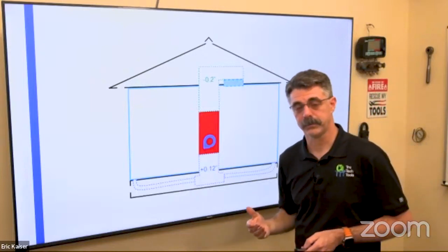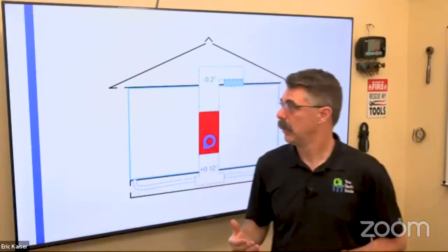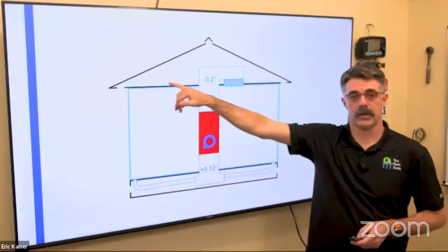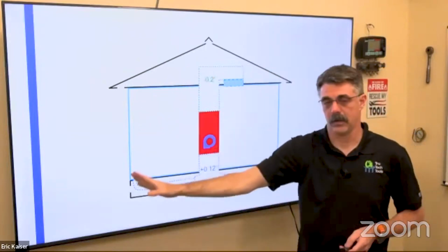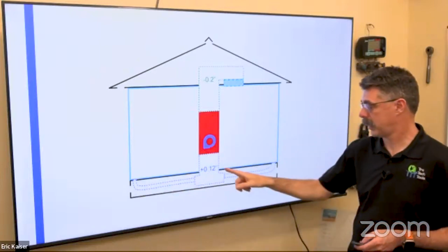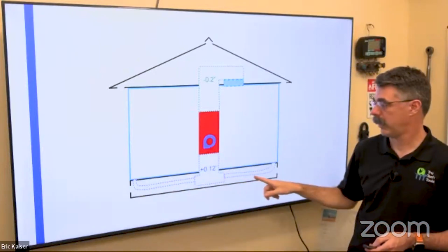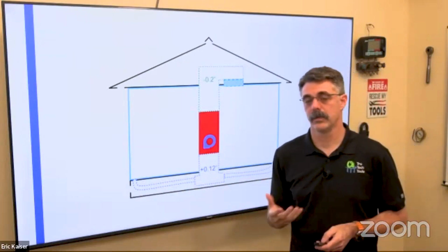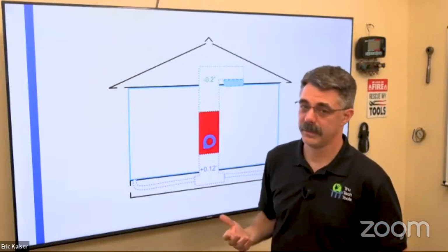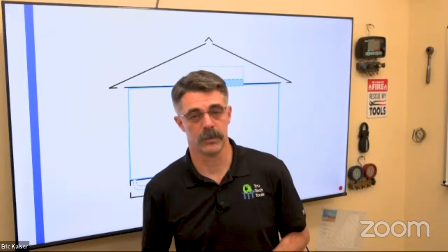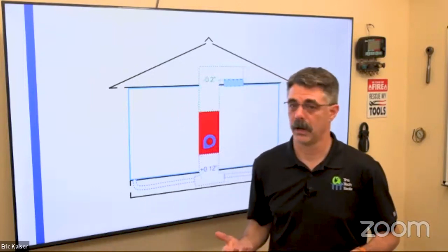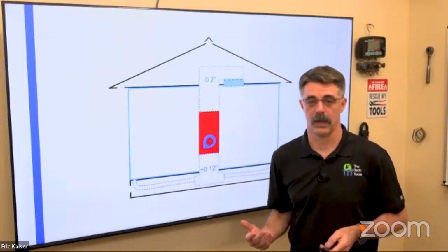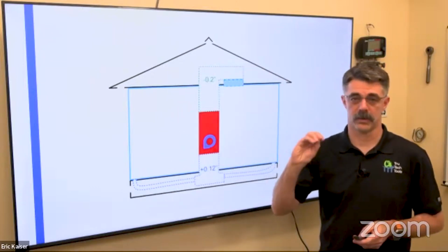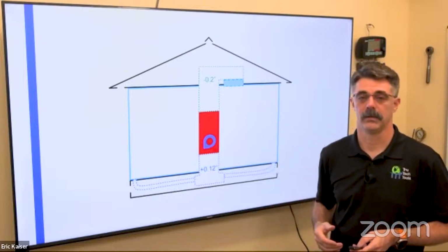Making sure those ducts are tight. One of the other pieces here is insulation. We try to do a really good job insulating everything up here in the attic and on the walls, and then we cut holes in and we move hotter and colder air through those ducts that have typically less insulation, because most of your residential ducts are at best an R8 insulated. And if that gets squished at all, the R value goes away.